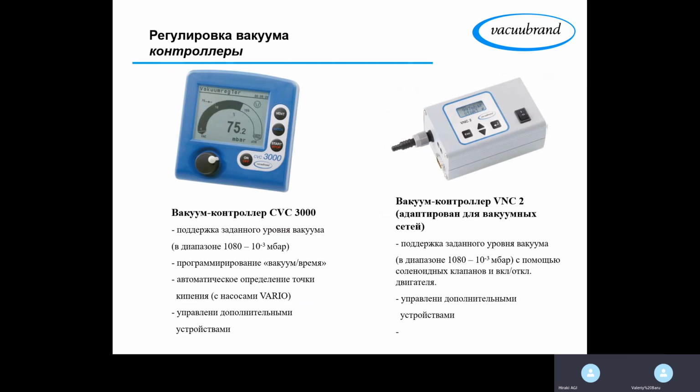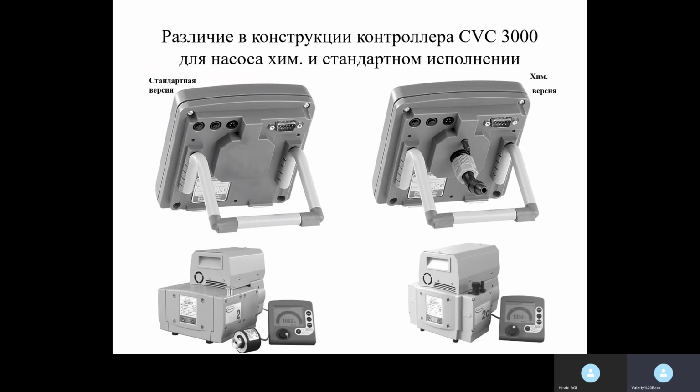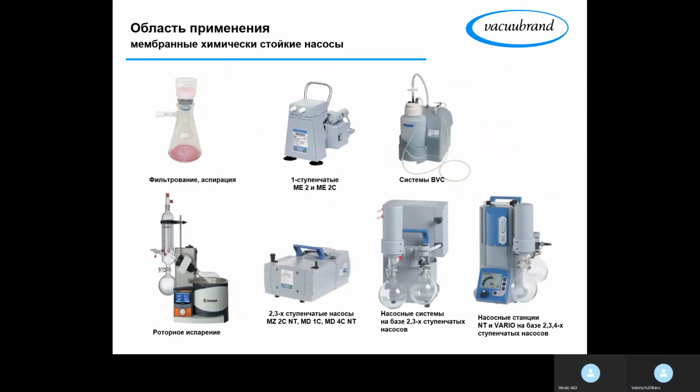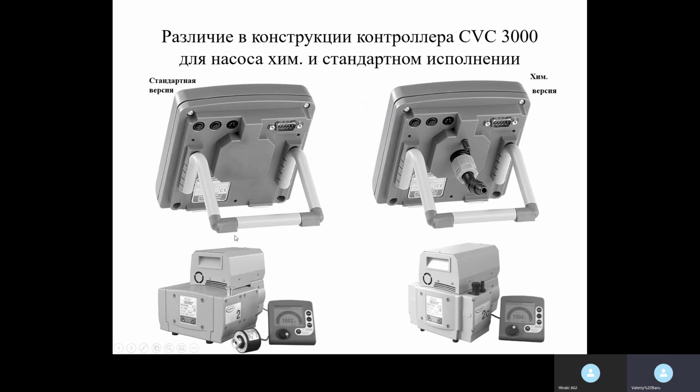Okay. So once you see a pump with a controller, at least from Welch and from Vacuubrand, you can say that you can define the boiling point. And by the way, another good thing: you can buy from both Vacuubrand and Welch only the controller and the vacuum valve.